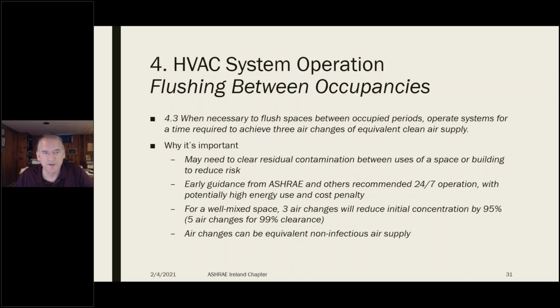that doesn't seem necessary. So our recommendation now is that when there's a need to flush a space between occupied periods, say between class periods when we're having a changeover of classes at a university, operate the system long enough to provide 3 air changes of equivalent clean air supply. Emphasis here on equivalent clean air supply. So it doesn't need to be 3 air changes of outdoor air.